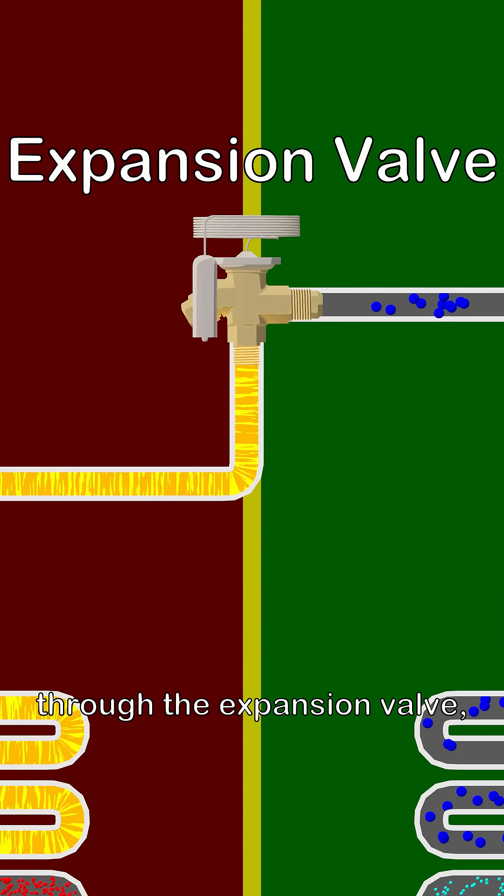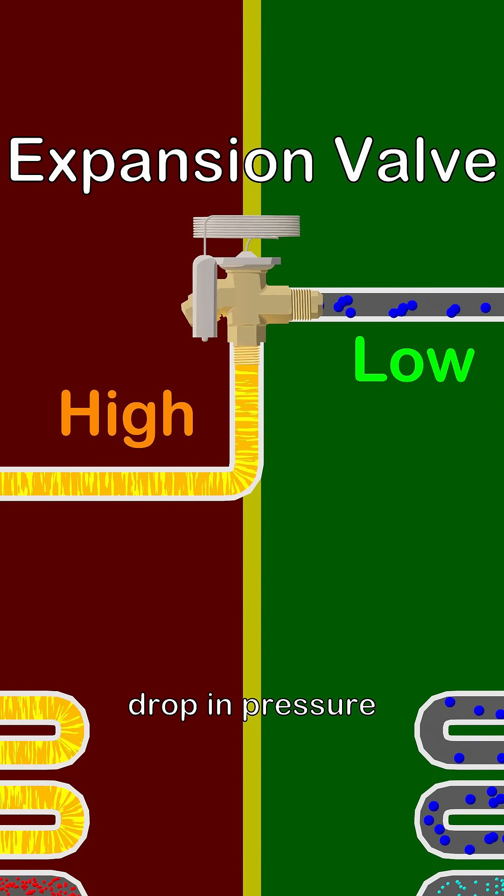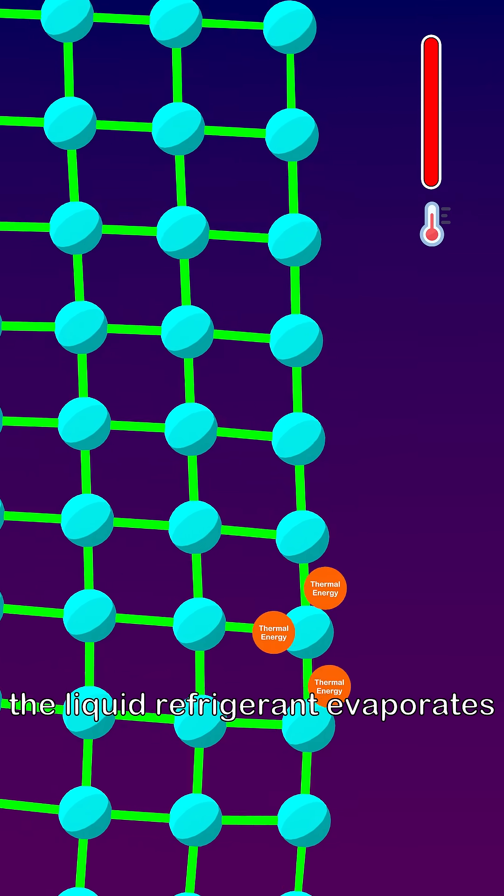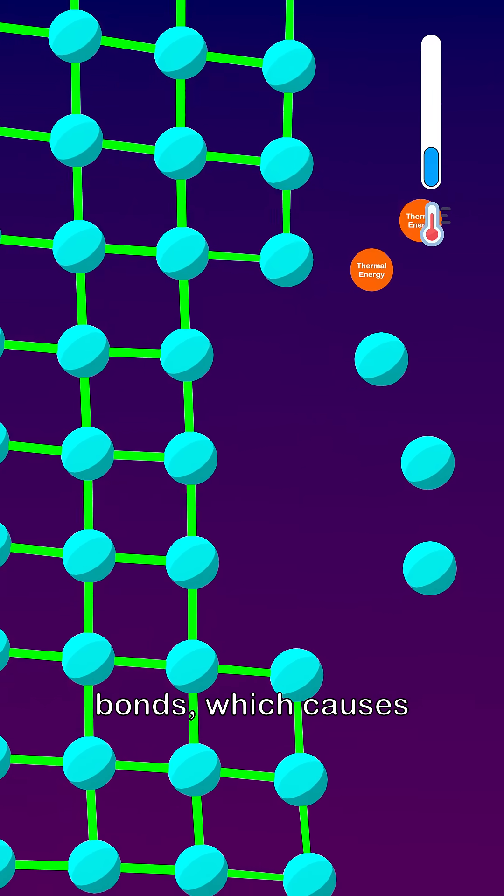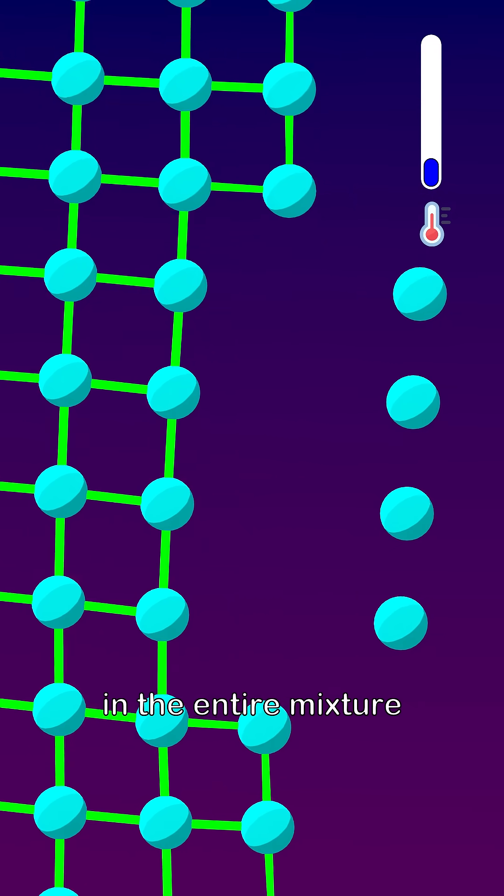As the refrigerant passes through the expansion valve, it experiences a sudden drop in pressure. In response, a portion of the liquid refrigerant evaporates by consuming its own thermal energy to overcome molecular bonds, which causes a significant temperature drop in the entire mixture.